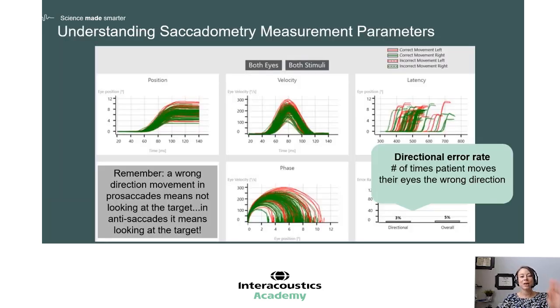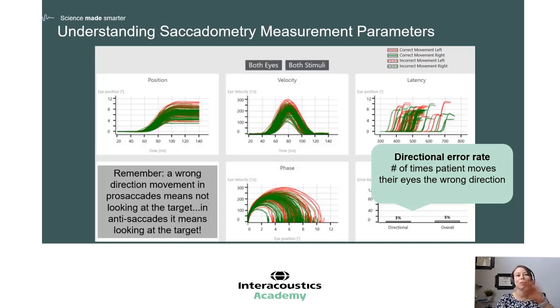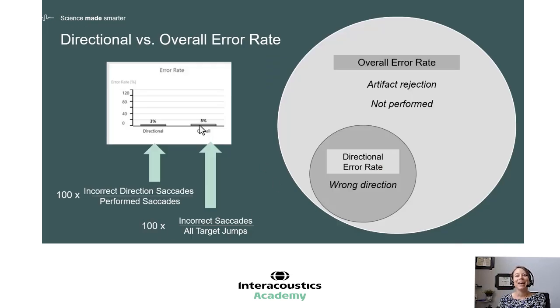There are five measurement parameters used in saccadometry, and a few are new compared to that random saccade test. The first is called directional error rate — simply the number of times the patient moves their eyes in the wrong direction. Remember that depending on the task, a directional error means something different. For pro-saccade, the patient is instructed to look towards the target, so a directional error means they're not looking towards the target. In anti-saccades, a directional error means they likely followed the dot instead of going the opposite direction. There's also an overall error rate shown on the summary screen — I'll describe that next.